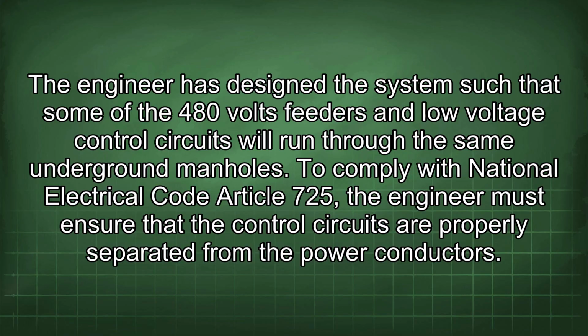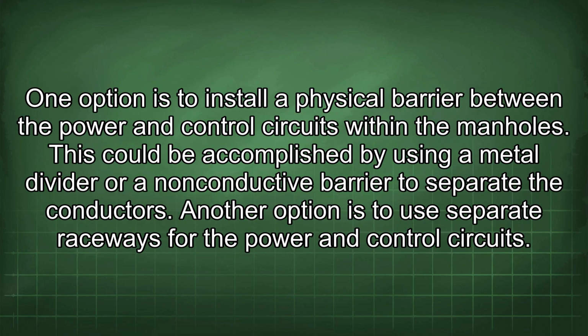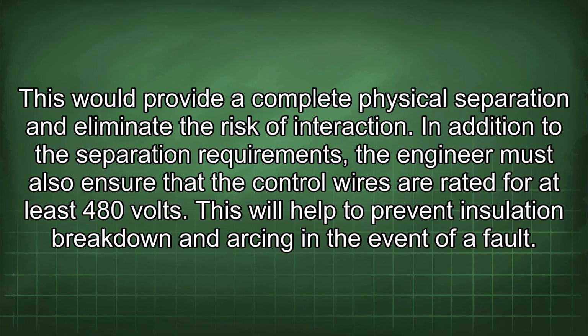To comply with National Electrical Code Article 725, the engineer must ensure that the control circuits are properly separated from the power conductors. One option is to install a physical barrier between the power and control circuits within the manholes. This could be accomplished by using a metal divider or non-conductive barrier to separate the conductors. Another option is to use separate raceways for the power and control circuits. This would provide a complete physical separation and eliminate the risk of interaction.